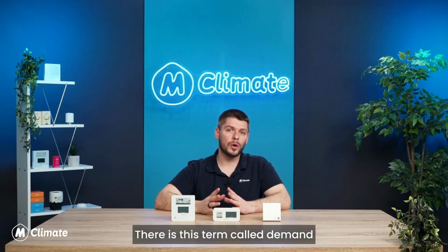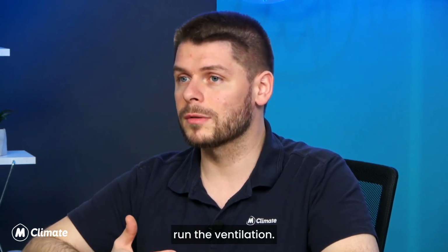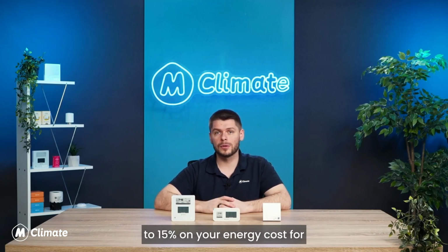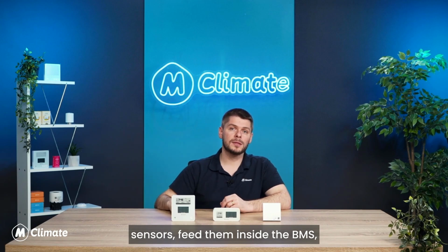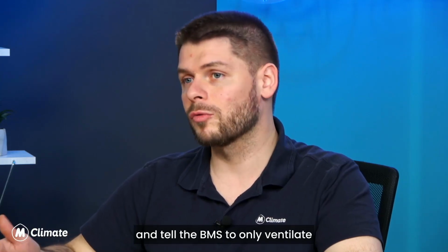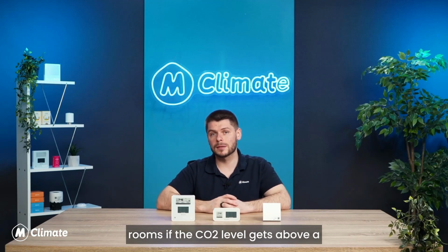There is this term called demand-driven ventilation. And usually inside buildings, it is a schedule-based ventilation. So they set from 9 o'clock until 5 o'clock, run the ventilation. The studies show that you can save 5 to 15% on your energy cost for ventilation if you do demand-driven ventilation, which means you take those readings from the CO₂ sensors, feed them inside the BMS, and tell the BMS to only ventilate rooms if the CO₂ level gets above a threshold, let's say 1000 ppm.